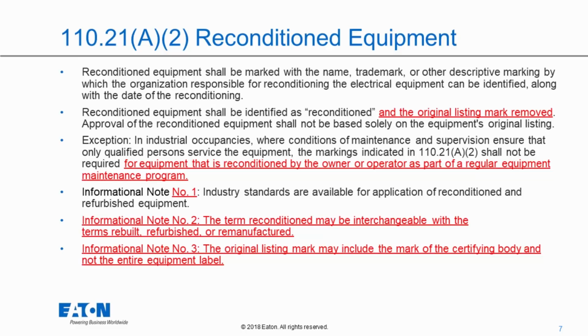If we look further into 110.21(A)(2), you'll see the first two requirements that we've talked about previously that were in the 2017 code. They did add, as mentioned, the removal of the original listing mark. Again, that's primarily to make sure that the original manufacturer is not responsible for the equipment after it's reconditioned. They also added in the exception that this refers to industrial occupancies, that the marking indicated in 110.21(A)(2) shall not be required for equipment that is reconditioned by the owner or operator as part of a regular equipment maintenance program.